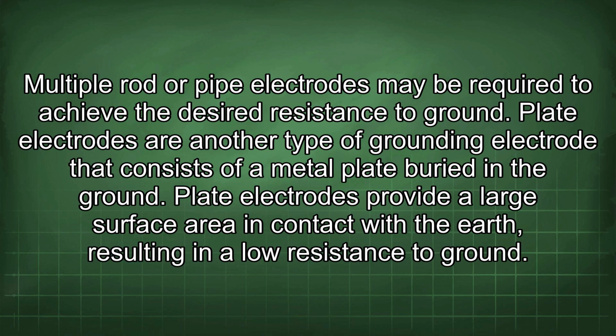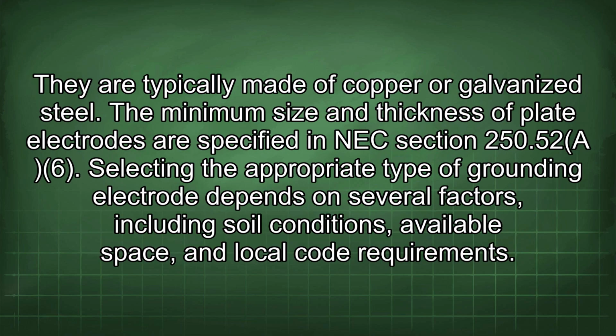Plate electrodes are another type of grounding electrode that consists of a metal plate buried in the ground. Plate electrodes provide a large surface area in contact with the earth, resulting in a low resistance to ground. They are typically made of copper or galvanized steel. The minimum size and thickness of plate electrodes are specified in NEC Section 250.52(A)(6). Selecting the appropriate type of grounding electrode depends on several factors, including soil conditions, available space, and local code requirements.